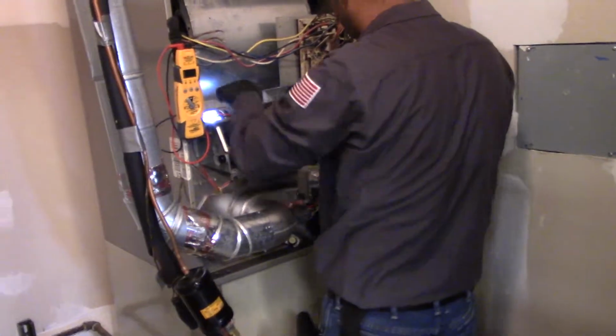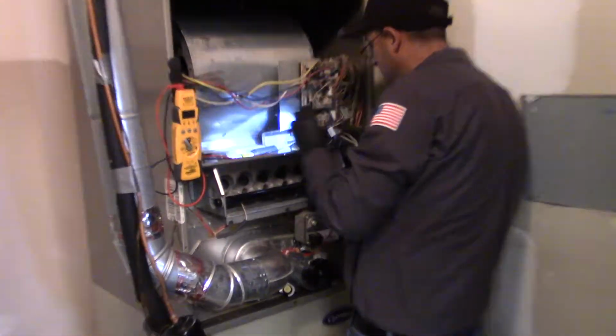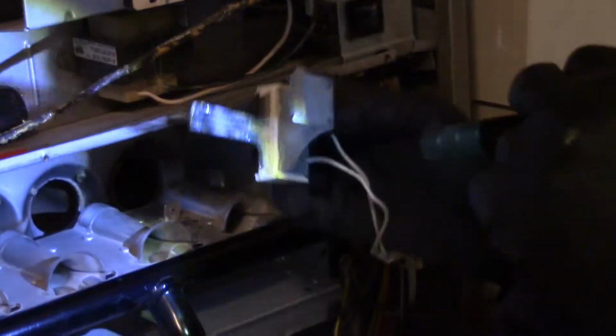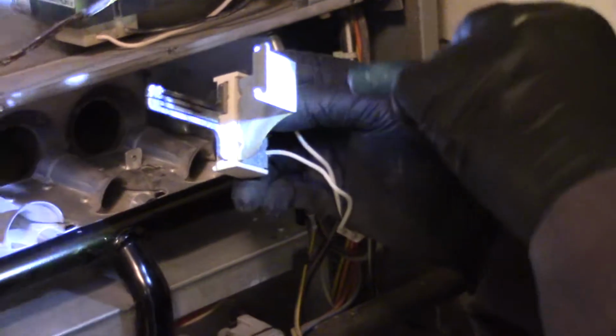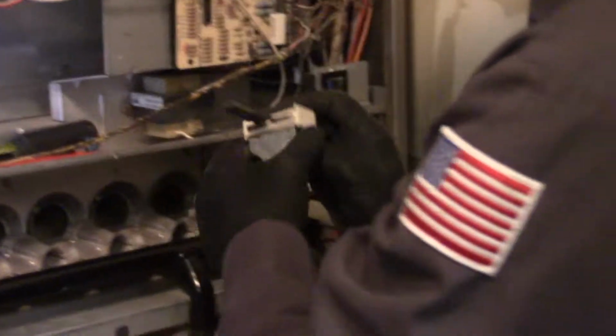You barely touch them and they break. So if we take a look at this one, we can see there's some changing in the color, it's turning white. Typically what that means is the igniter is going bad. That's a good indication if we see a lot of that. If you don't see a nice shiny color, and see more of this discoloration -- I think the word might be oxidizing -- it's starting to wear and tear.